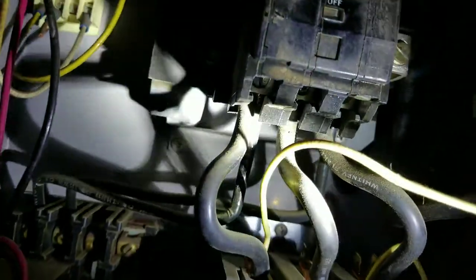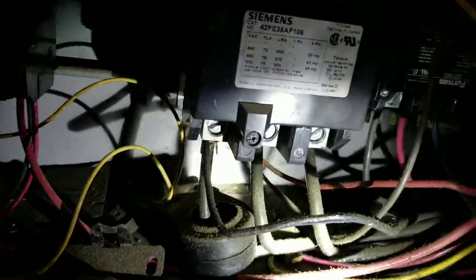Here's my main panel. I just did a little bit of visual inspection of what was going on. Let me get my flashlight. I basically looked around for any burn marks — that's the visual inspection. This is a big cluster in here anyway; look at these wires running everywhere. It's crazy — surprising there aren't any other shorts. I didn't see any physical shorts around the contactor, so I followed my wires going up — these ones right here — they go up through my conduit right here.